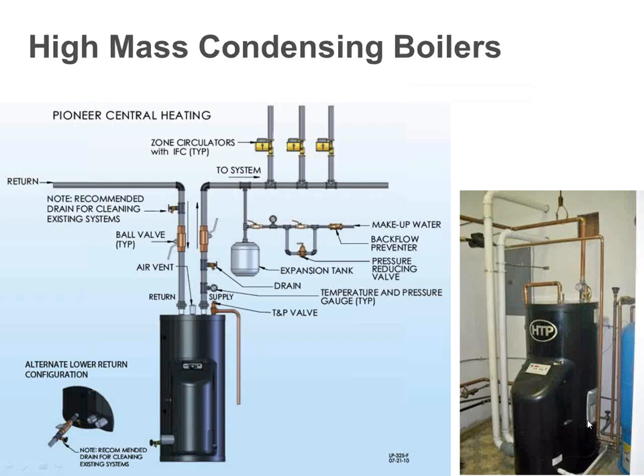Okay. It's just an example of it. As you can see, this is Grandpa's piping. Boiler in, boiler out. That's all there is to it out to the system. Okay, so it's a very, very simple system, and it's due to the high mass of the boiler. So it's very compact. As you can see, it still vents in PVC because it is a condensing boiler.